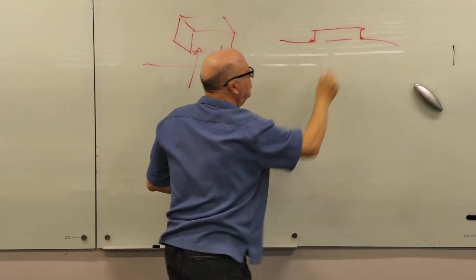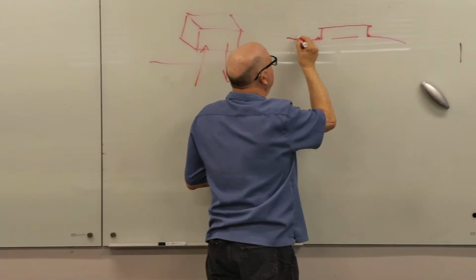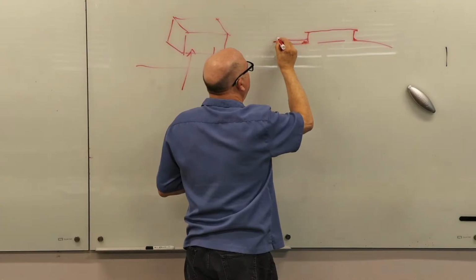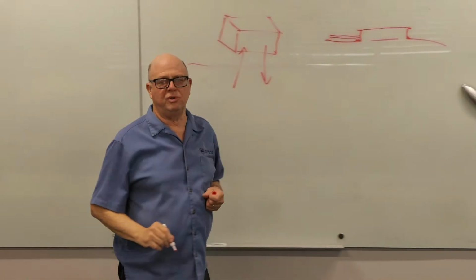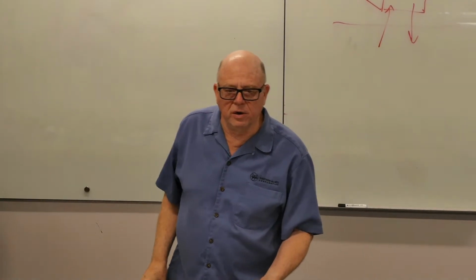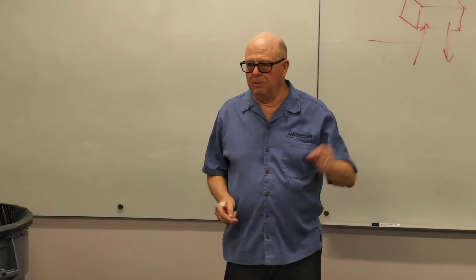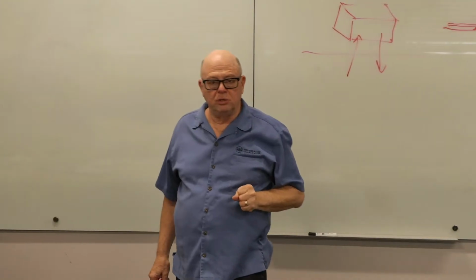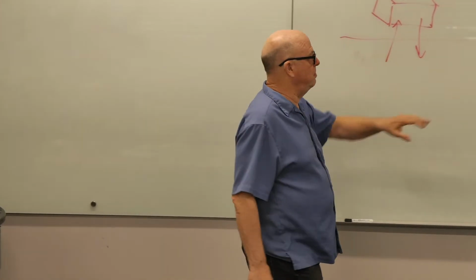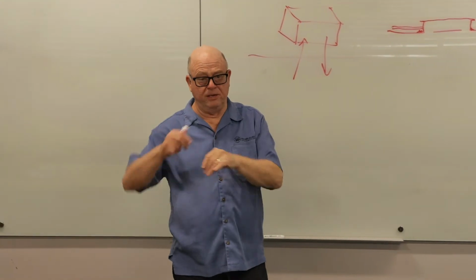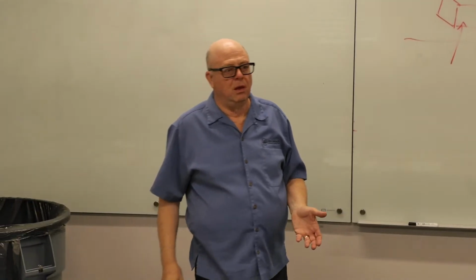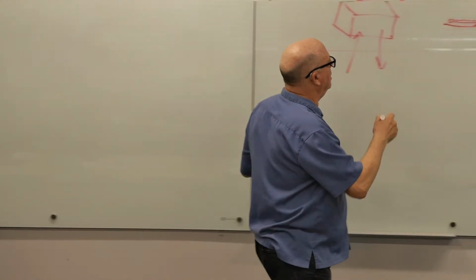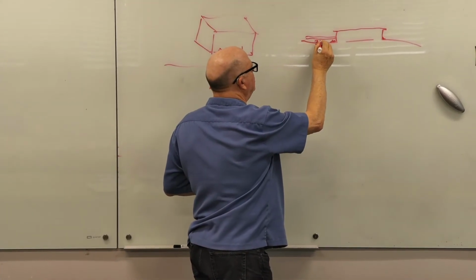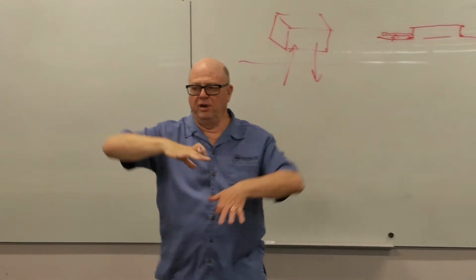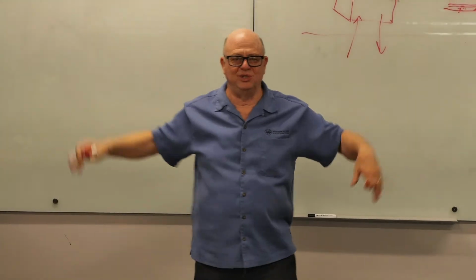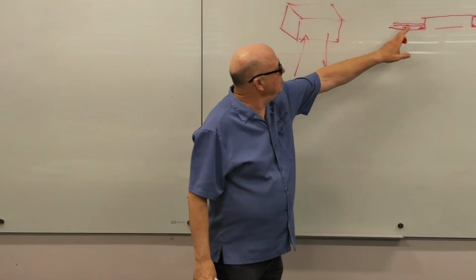You attach this curb however you're going to attach it to the structure, and then the layer of insulation comes in, and then your waterproofing layer comes in. So 35 years ago when I was the Carrier salesman, the energy code requirement for this insulation was not much. In fact, if it wasn't conditioned space, there was virtually no insulation requirement. If it's conditioned space, then there was some requirement. Well, that's changed over 35 years. Where this might have been maybe 2 inches of insulation, plus whatever you allow for an uneven application of the waterproofing membrane, half an inch, probably less than an inch, so maybe it's 3 inches tall.